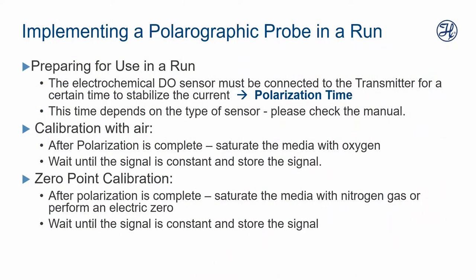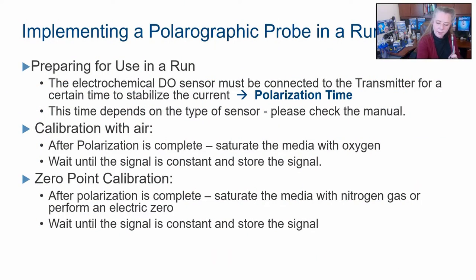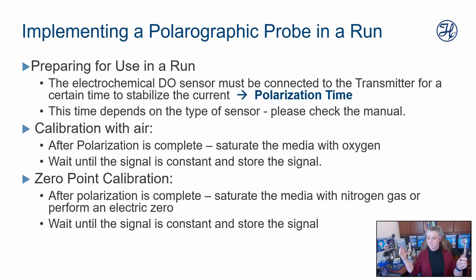So as Doug was saying, how the heck do I get my probe to be usable? This is specific to polarographic probes, okay? So you cannot, once you've rebuilt the probe, put it in and expect it to work. It doesn't. It needs to, as we just talked about, polarize. By polarization, we mean we need to connect the probe to the transmitter in liquid for some amount of time to stabilize the current. It's called polarization time.